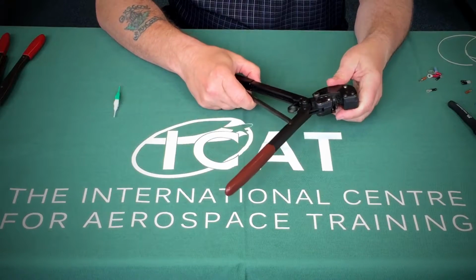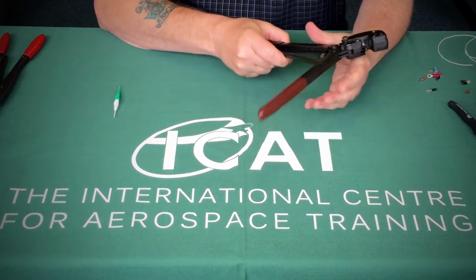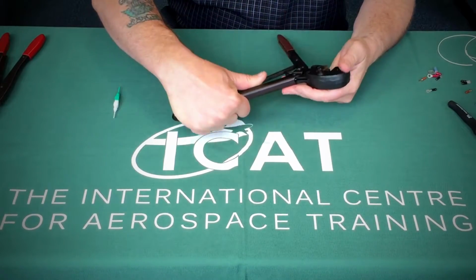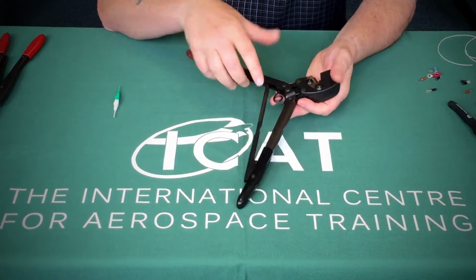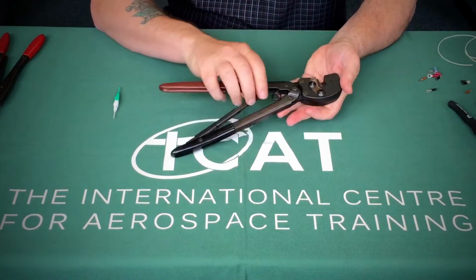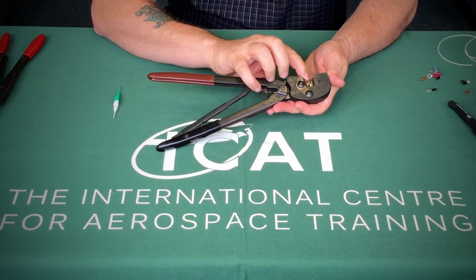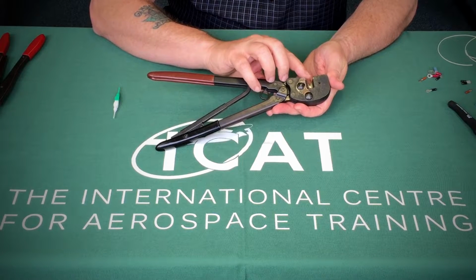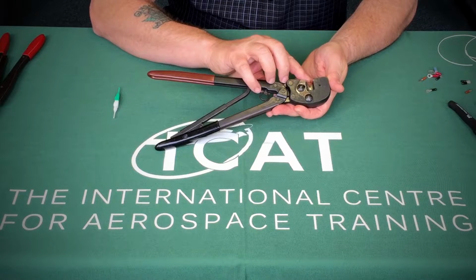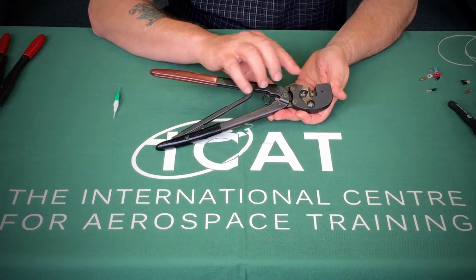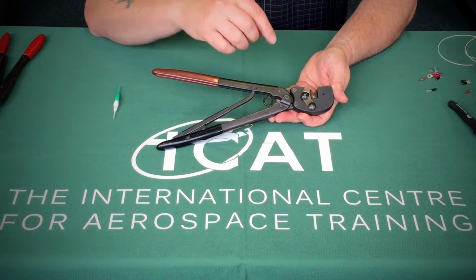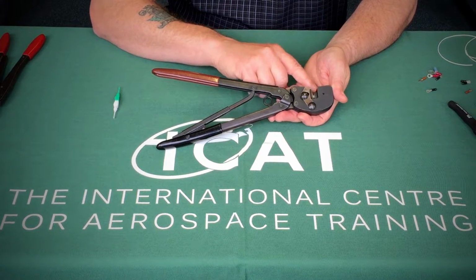Other things we should be checking for prior to use are obviously that there are no missing bolts or connectors. On this side, if we close it up slightly, you'll see there's a little locating device. That locating device allows me to fit the crimp in the tool correctly, so that when the crimp is formed, it is formed in the correct position.